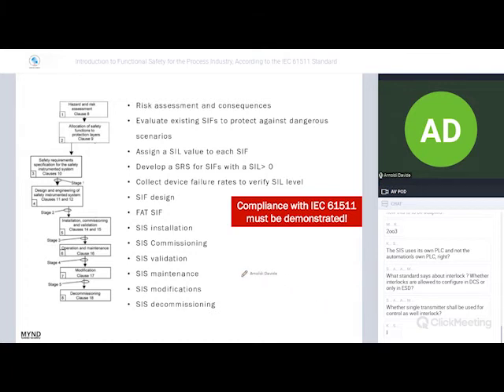I'm just summarizing what is normally provided during the functional safety design. So we can speak about risk assessment and consequence, that is HAZOP. Then we have to evaluate the safety instrumented functions, assign the SIL level to each SIF, and develop the safety requirement specification of each SIF. This is a technical requirement of each safety instrumented function. And then we also have to realize the FAT, installation, commissioning, and so on. Everything is related to the safety instrumented system only.